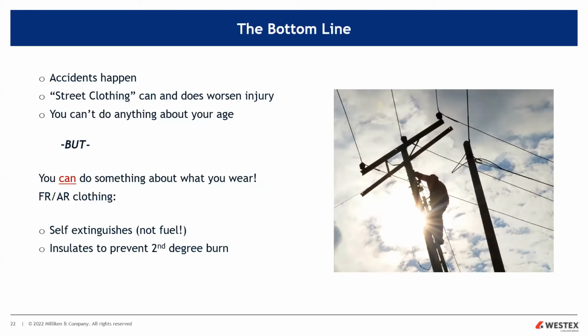Job 2 is the arc rating. That's your insulative piece. That protects you from getting a second-degree burn through the fabric. For instance, if you have a fabric that has an 8.7 arc rating, what does that mean? That means that if I'm exposed to 8.7 calories per square centimeter, there's a 50% probability that there'll be enough heat transfer through that fabric to predict the onset of a second-degree burn through the fabric based on the Stoll curve. So job one, self-extinguish. Job two, insulate, prevent the second-degree burn. Why are we trying to prevent the second-degree burn? Because as I showed you a few slides ago, second-degree burn causes blisters. That's an infection pathway. So we want to prevent blistering.